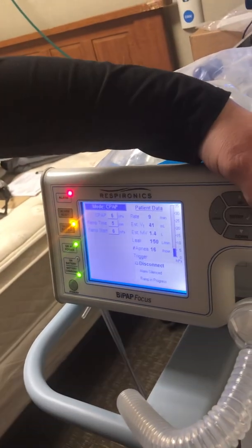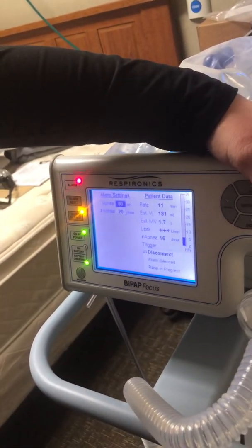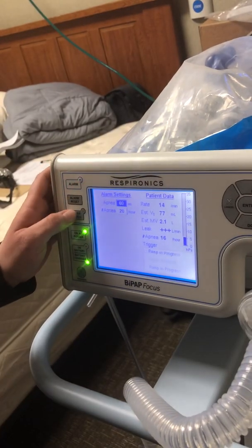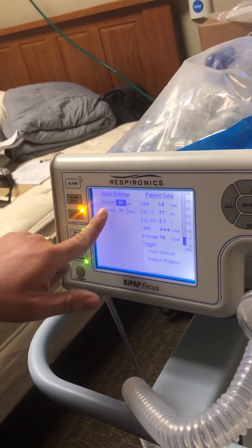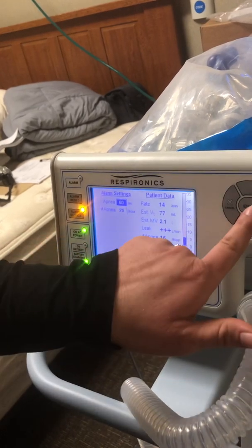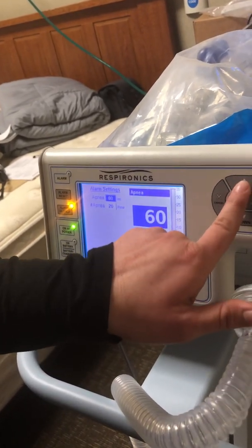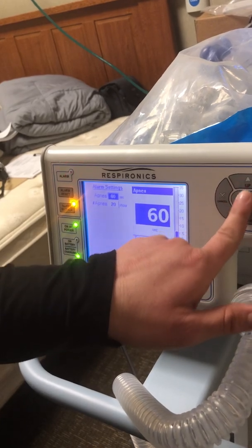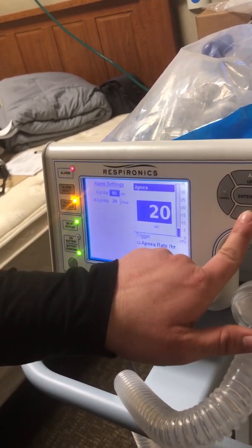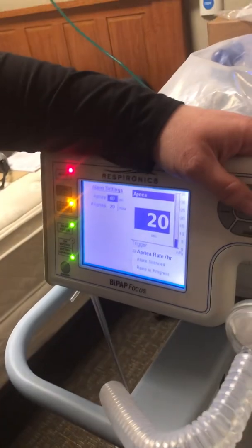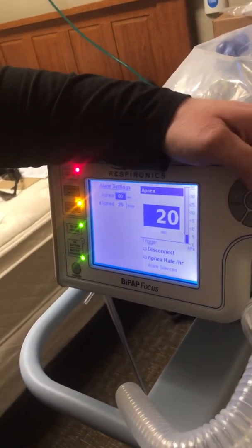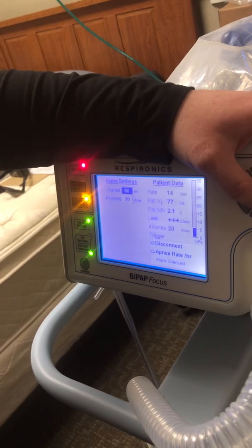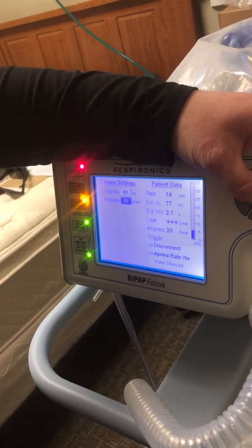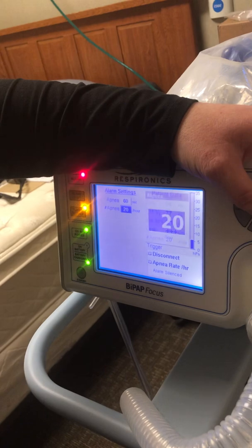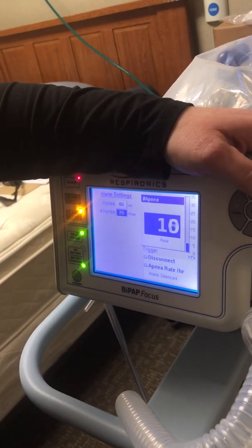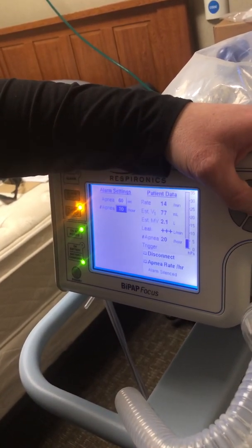So here you can go over the change, anything like your alarm. So you'd hit your change screen. You can set it to have alarm settings for apnea for every 60 seconds. If you want to change that, you can go up higher or you can go lower, so max 60 seconds. So you can have it check every 60 seconds alarm. And then down here it will do 20 per hour. So here you can change it down to 5 per hour, 10 per hour, anything like that.